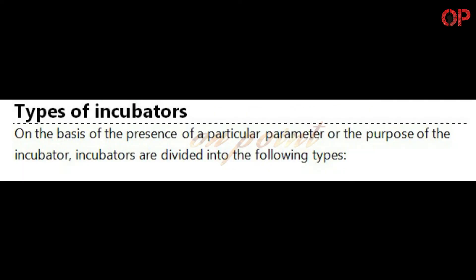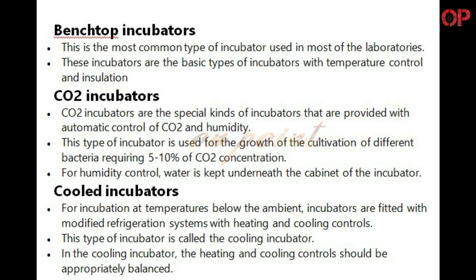Types of Incubators: On the basis of the presence of a particular parameter or the purpose of the incubator, incubators are divided into the following types. Benchtop Incubators: This is the most common type of incubator used in most laboratories. These are the basic types of incubators with temperature control and insulation. CO2 Incubators: CO2 incubators are special kinds of incubators provided with automatic control of CO2 and humidity. This type is used for the cultivation of different bacteria requiring 5–10% CO2 concentration. For humidity control, water is kept underneath the cabinet of the incubator.